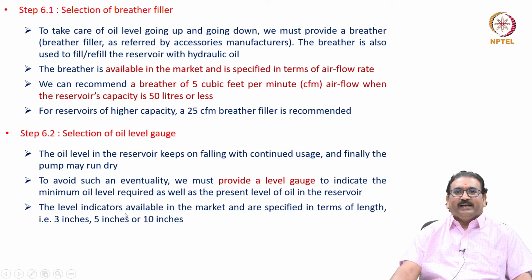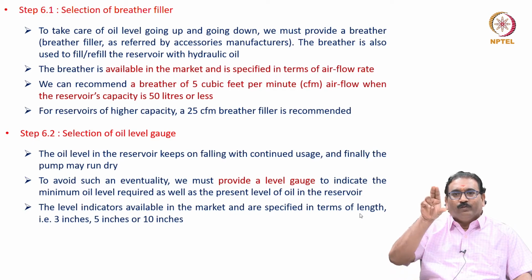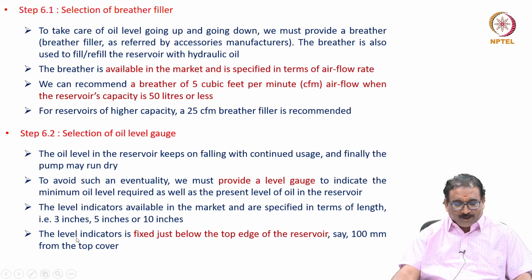The level indicators available in the market are specified in terms of length. You may get 3 inch, 5 inch, 10 inch, 20 inch, based on your requirement, visibility, and clarity. You will mount it over the tank, where the level indicator is fixed just below the top edge of the reservoir, say 100 mm from the top cover.